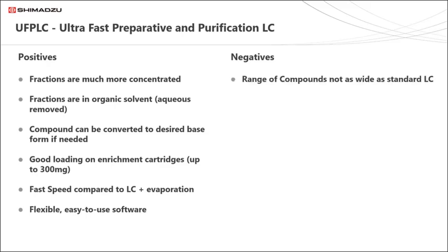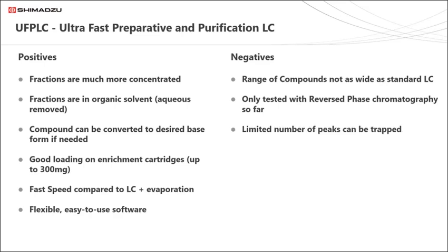Negatives. The range of compounds is not as wide as standard LC. Only tested with reverse phase chromatography so far, and a limited number of peaks can be trapped.